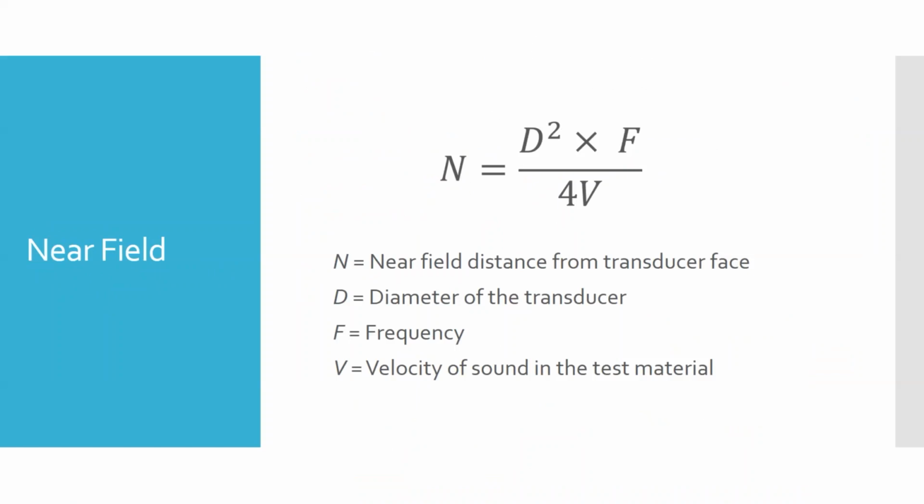Well, one way to do this is they tune probes for a certain frequency. Some of the probes we have are designed, they'll say on the probe that they should be run at 5 megahertz, or they should be run at 10 megahertz. And then they also know what the material is in the wear plate right here.